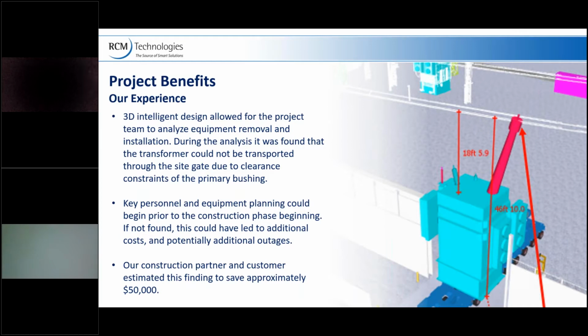Another example: a transformer was being moved through the station gate, shown here on the right. Our team modeled the equipment our construction partner would be using, followed the procedures they wanted to use, and simulated what would occur with all the equipment there. We found immediately that if the high voltage primary bushing of this transformer was kept on, there'd be a huge clearance issue to an energized overhead line, and it wouldn't be possible this way. If this wasn't found so early in engineering, it would have caused additional key personnel, additional equipment, time, and schedule delays — overall a cost impact of around $50,000 onto the project, almost a no-brainer to find when you have these 3D intelligent tools available.